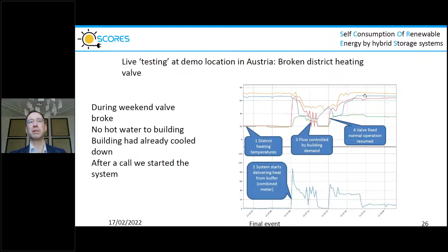You can see the system delivered energy. Temperatures inside the buffer go down while temperatures inside the building go up. Around here you reach some kind of equilibrium where the building is back up to temperature and people are comfortable. At about 3 in the afternoon, the district heating was repaired, the system switched off, the temperatures inside the district heating system go up, and the buffer is replenished.